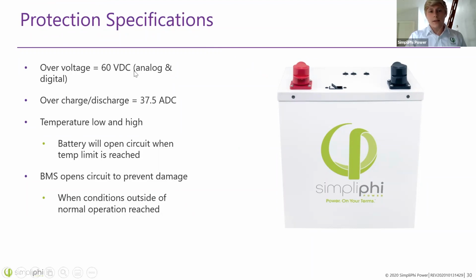The battery communicates its set points to the solar converter, like I said. So those set points are 37.5 amps DC and 60 volts DC for overvoltage protection. And it's going to have 2 lines of protection. One within the inverter, telling the inverter to, hey, please cut off charging when I reach 60 volts. That's the absolute maximum worst case scenario. Really, these batteries should be charging to 56 volts, and this 60 volts is just kind of a backup protection.